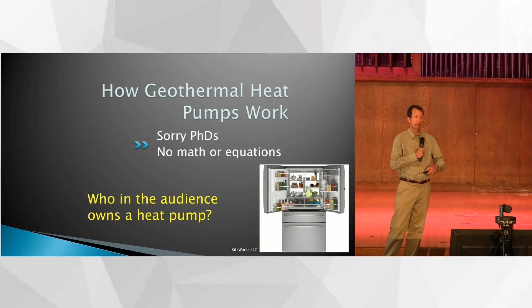So geothermal boreholes — this is a picture on the left. It is not a well. In a well, water flows into or out of the well. This is a drilled hole in the ground. A piece of plastic pipe is looped into that hole, and then it's grouted in place, so water flows through that pipe and transfers heat to or from the ground. It can be installed in very large facilities, like the university here in Toronto — in fact, the library on campus is geothermal heat pump heated — or it can be in a small building like this house.